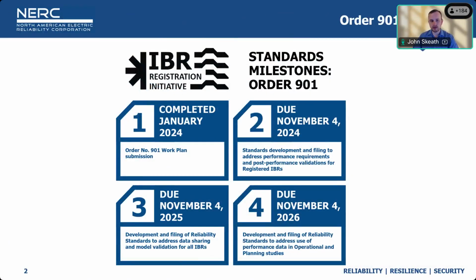PRC-029 was developed as part of a 4-milestone goal from FERC Order 901. The first milestone is largely just the work plan associated with the remaining milestones to address all the directives within FERC Order 901. FERC Order 901 was released coincidentally with the IBR registration initiative, which is also in response to a FERC order that essentially says we need to register additional inverter-based resources in order to ensure the reliable performance of the aggregate fleet of inverter-based resources on the bulk system. So this is developed as part of the standards revisions to address the performance that is expected of registered IBR categories.